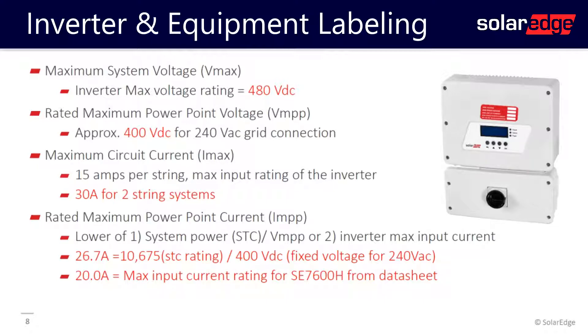SolarEdge is a little tricky in the fact that we don't have a VOC. The VOC is your open circuit voltage, and it is recorded for SolarEdge as our safety voltage, which is one volt per optimizer. That doesn't tell us very meaningful safety information. So instead of VOC and ISC, we are going to write VMAX and IMAX.